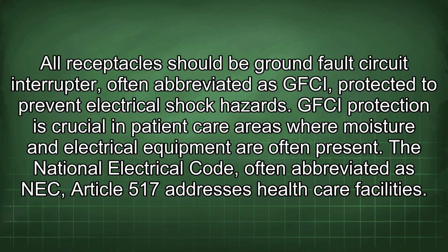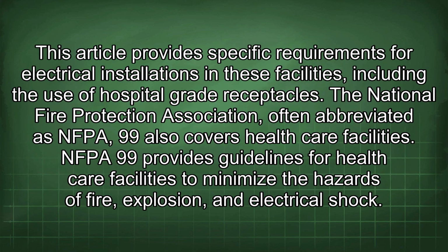All receptacles should be ground fault circuit interrupter, often abbreviated as GFCI, protected to prevent electrical shock hazards. GFCI protection is crucial in patient care areas where moisture and electrical equipment are often present. The National Electrical Code, often abbreviated as NEC, Article 517 addresses healthcare facilities. This article provides specific requirements for electrical installations in these facilities, including the use of hospital-grade receptacles. The National Fire Protection Association, often abbreviated as NFPA 99, also covers healthcare facilities. NFPA 99 provides guidelines for healthcare facilities to minimize the hazards of fire, explosion, and electrical shock.